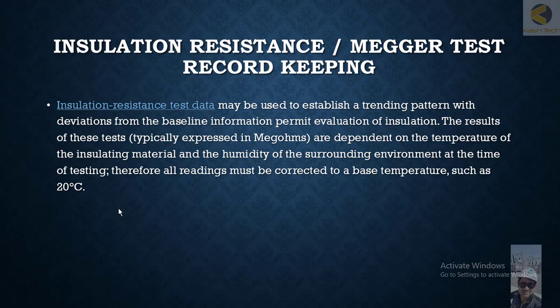It is most important that whatever reading you are getting, you should convert it to 20 degrees centigrade each time, so you can compare values year over year, because the reading is affected by temperature. If you are not using the correction factor or multiplying factor, you will not be able to analyze the pattern of insulation — whether it is going down or not — and the readings will be quite random.